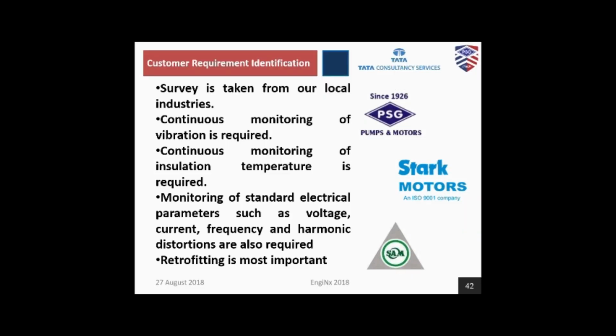The customer requirements were identified based on a survey taken from local industry. Based on the survey, it was identified that continuous monitoring of vibration in the pumping system was required, as well as continuous monitoring of insulation temperature. Monitoring of standard electrical parameters such as voltage, current, frequency and harmonic distortions, along with the above parameters, are possible only with retrofittings. This was the conclusion made from our survey.